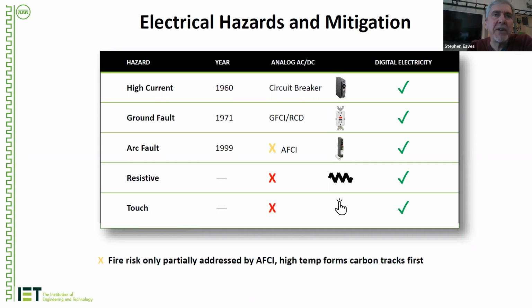The conventional devices, whether it's arc fault or ground fault or circuit breakers, aren't able to detect the shock value in terms of current, even if you are at very dangerous levels of electrical current through your body. The closest thing you might imagine is a ground fault detector, but ground fault detectors are looking for a sort of sneak path through a ground, like a faucet or something like that. And there is no ground path in a double insulated device. And even with a ground fault protected circuit, if you touch the hot and the neutral, it won't be detected by ground fault. Ground fault only detects from the hot to earth.